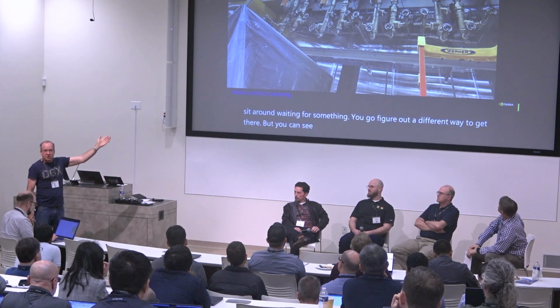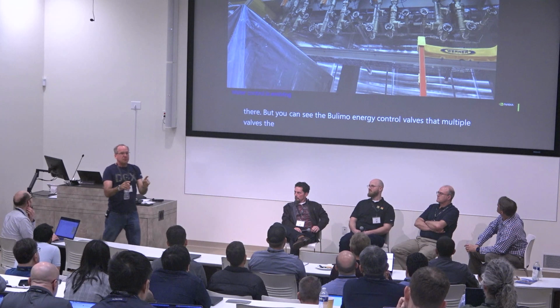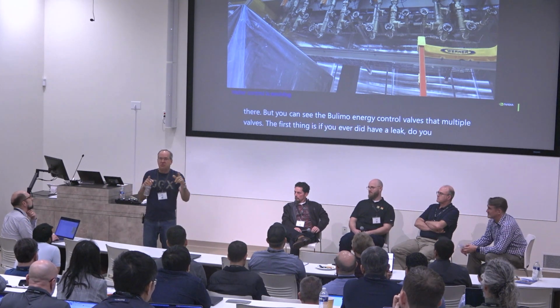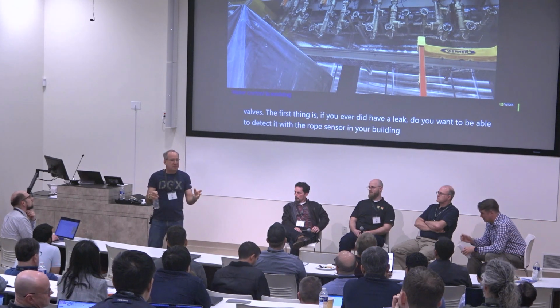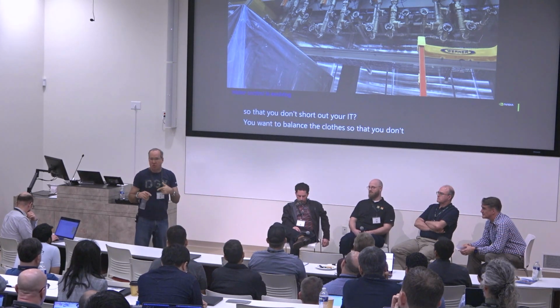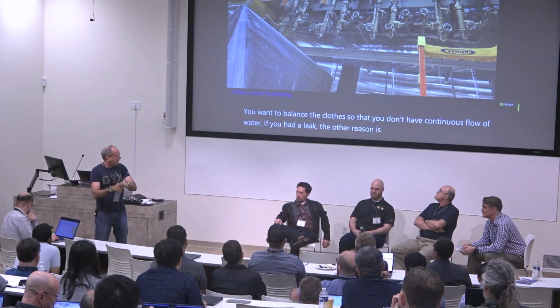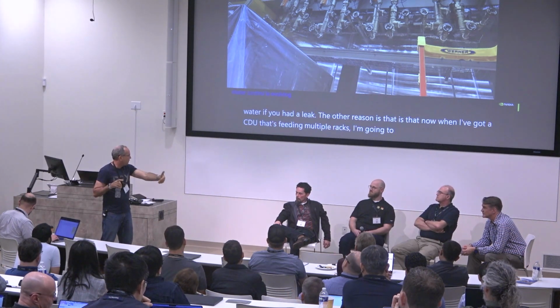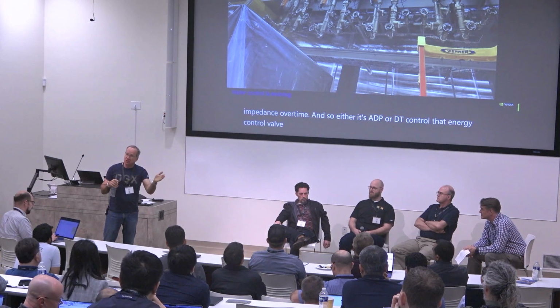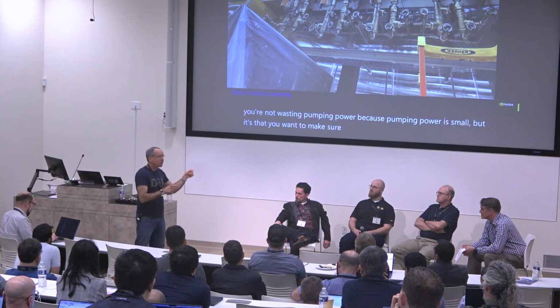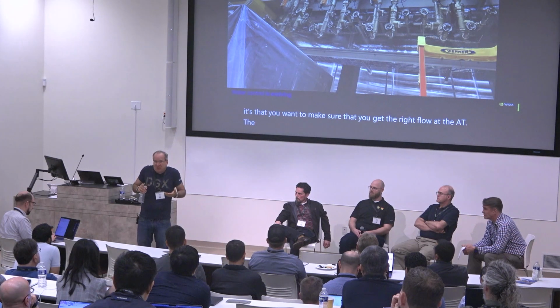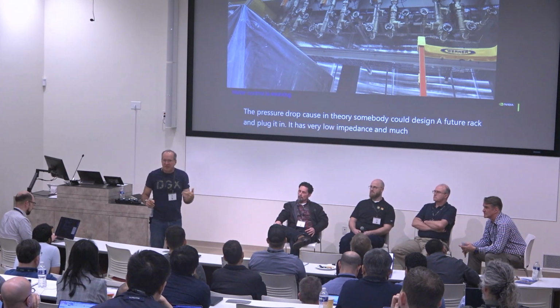But you can see the Belimo energy control valves, the multiple valves. The first thing is, if you ever did have a leak, you want to be able to detect it with a rope sensor in your building management system, so that you don't short out your IT. You want the valves to close so that you don't have continuous flow of water if you had a leak. The other reason is that now when I've got a CDU that's feeding multiple racks, I'm going to have different flow and impedance over time. And so either it's a DP or a DT control, that energy control valve opens and closes for the flow rate. That way, it's not that you're wasting pumping power, because pumping power is small, but it's that you want to make sure that you get the right flow at equivalent pressure drop. Because in theory, somebody could design a future rack and plug it in that has very low impedance and much lower power, and literally it would steal all your water.